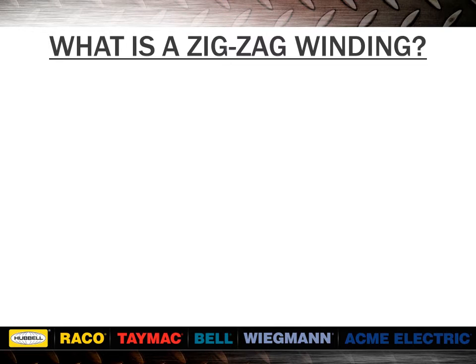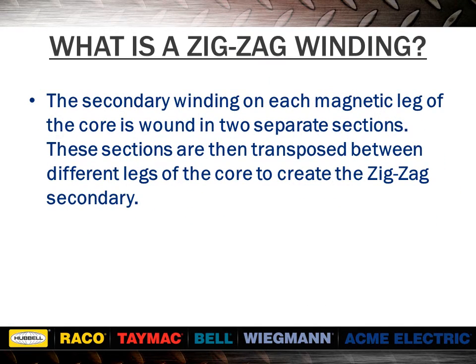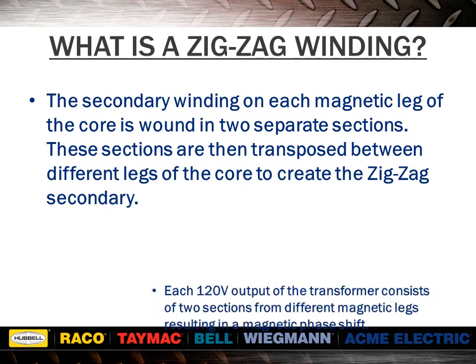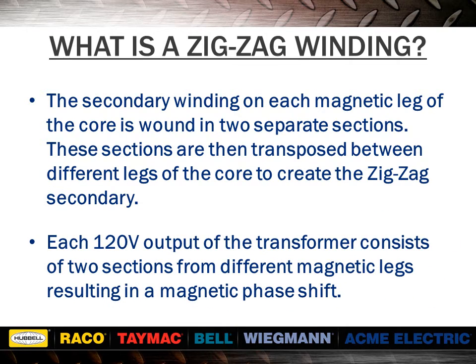The secondary winding on each magnetic leg of the core is wound in two separate sections. These sections are then transposed between different legs of the core to create the zigzag secondary. Each 120-volt output of the transformer consists of two sections from different magnetic legs, resulting in a magnetic phase shift.